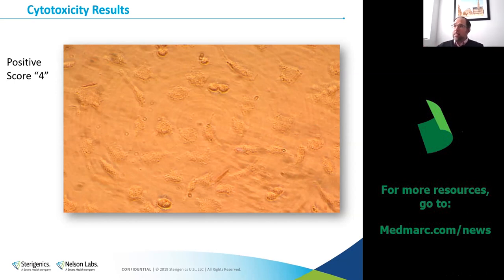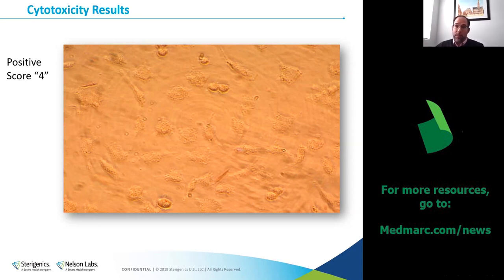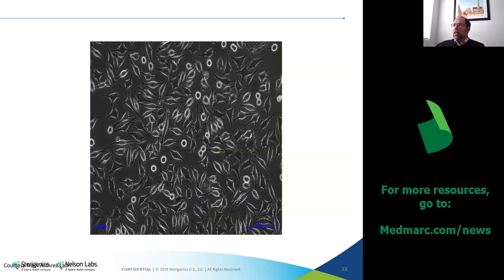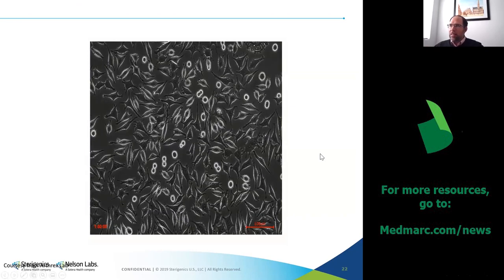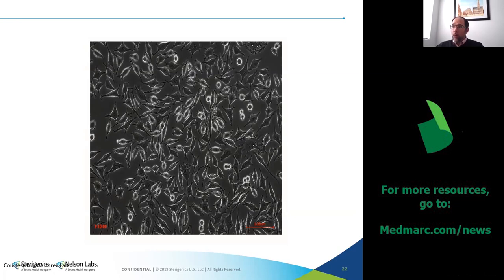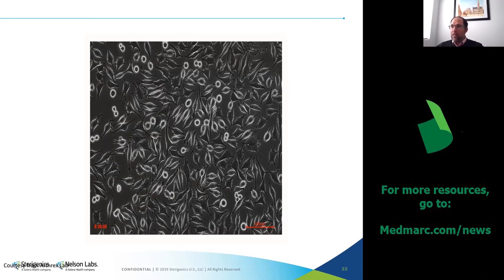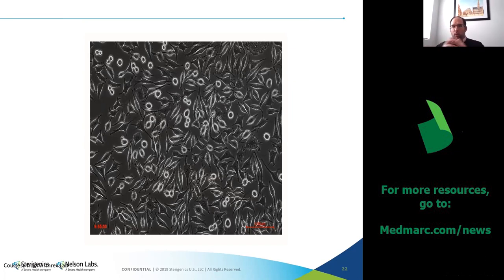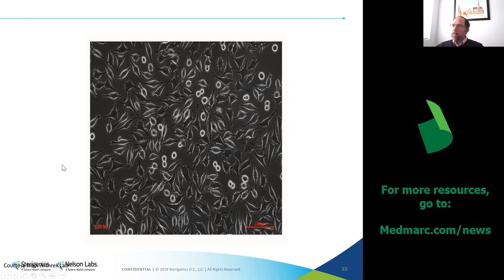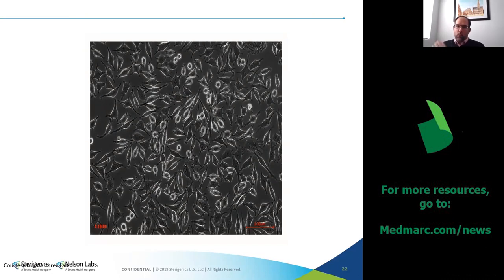The cell line under a microscope — this is what we want to see: a zero, a great mosaic pattern of cells on the bottom of the plate. The neutral red stain, a viable stain, means healthy cells will absorb and metabolize it, so we want to see that red. Compared to a four, there's a pretty big difference. The hard part of this test is scoring when you're between a two and a three — that takes skill, which is why quantitative tests are preferred. These cells you see — even those that look like cell skeletons — are from latex, our positive control, which is a fixative that burns that skeleton to the bottom of the plate.